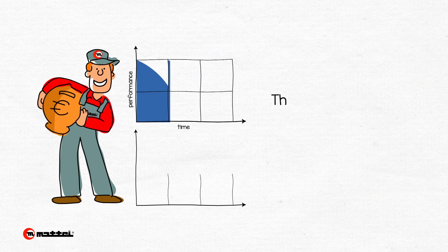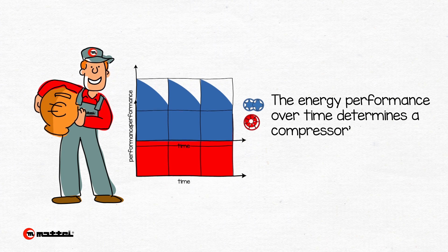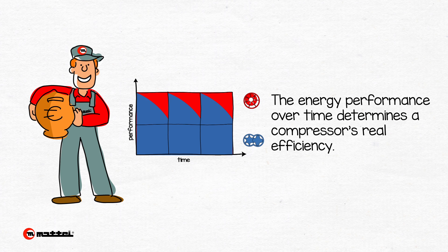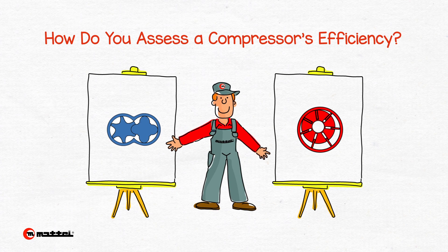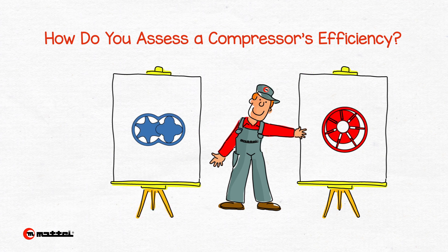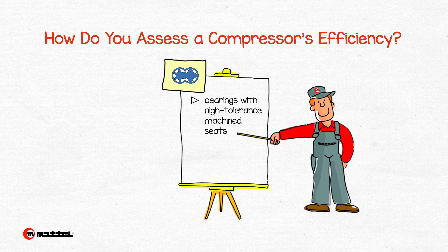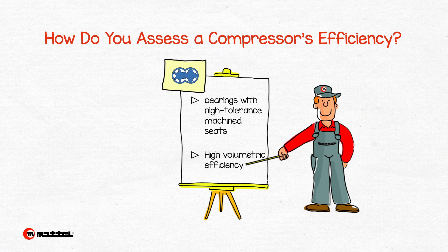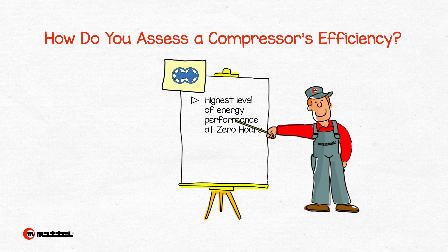In order to safely compare a screw compressor and a rotary vane compressor, it is necessary to consider the energy efficiency over time of both products. The screw compressor has bearings — ball and thrust — with high tolerance machined seats, permitting the bearings to work with minimum play and resulting in high volumetric efficiency. At zero hours, a screw compressor presents the highest level of energy performance of its operating life.